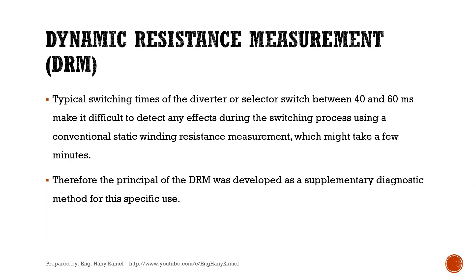Dynamic Resistance Measurement (DRM). Typical switching times of the diverter type or selector type OLTC switch between 40 and 60 milliseconds. This makes it difficult to detect any effects during the switching process using a conventional static winding resistance measurement, which might take a few minutes. Therefore, the principle of the DRM was developed as a supplementary diagnostic method for this specific use.